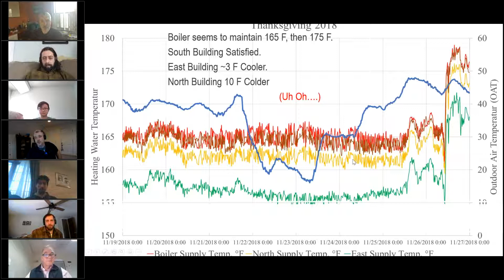So they did actually upgrade that system by making it primary, secondary, tertiary, and putting in a dedicated boiler pump for each boiler, making sure there's an adequate amount of supply going through each boiler. And then there's a boiler room loop that circulates water, and 3 takeoffs, one for each building, each one with their own pump, to make sure each building gets the appropriate amount of GPM. And that did help out with the problem and solve that north building being lower in temperature than the other 2. But is that the only problem going on here at the facility?